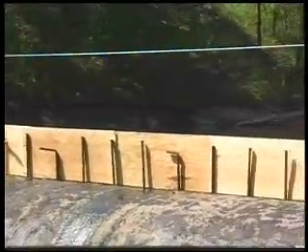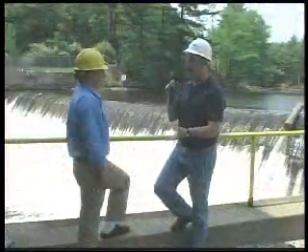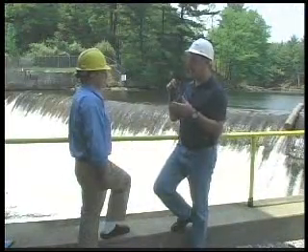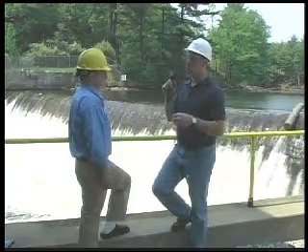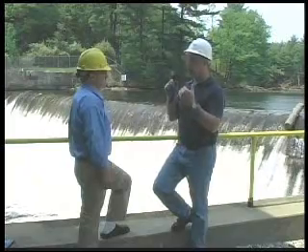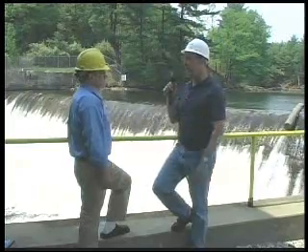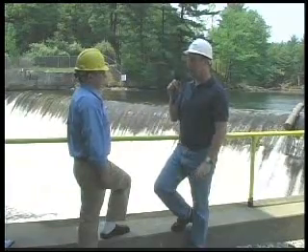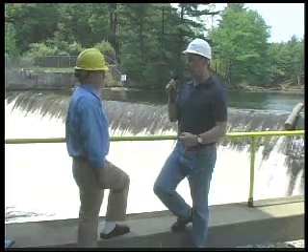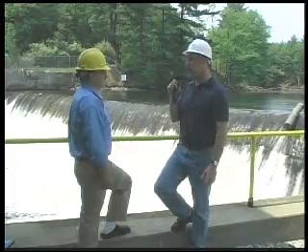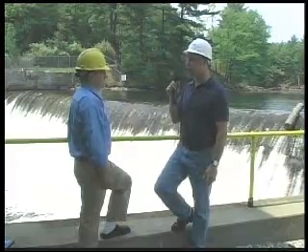When we talk about them, what we want to say is they trip, they go down. It's not really a failure. A failure of a flashboard is when they don't trip. What we wanted to indicate, though, is that those only trip when the water levels get above about 1.5 feet to about 2 feet above the boards in order to push them out. Once they're up there and we are under a flood condition or a high water event that's greater than our hydraulic capacity, we have no capability of removing those particular flashboards.